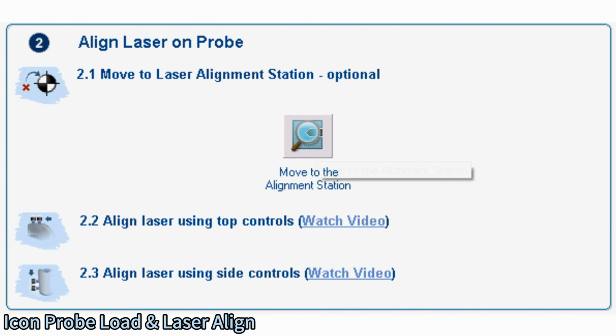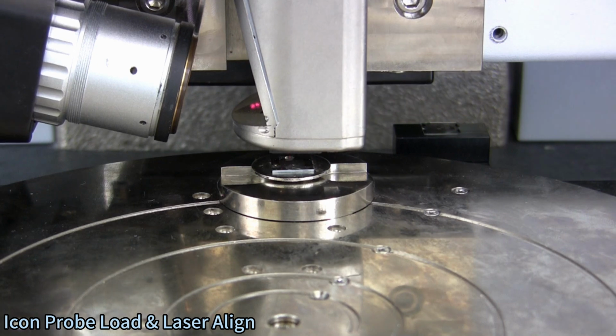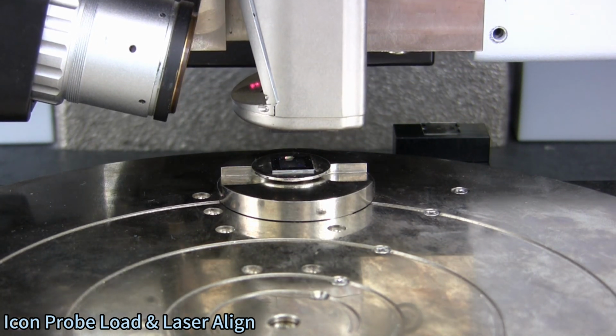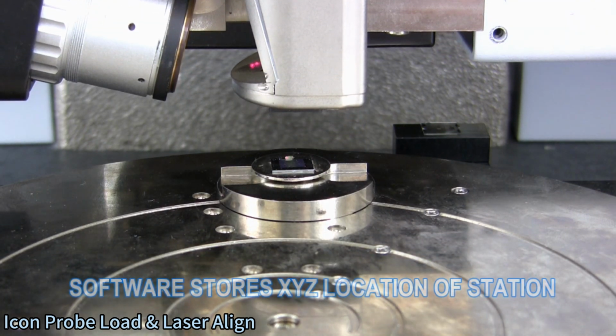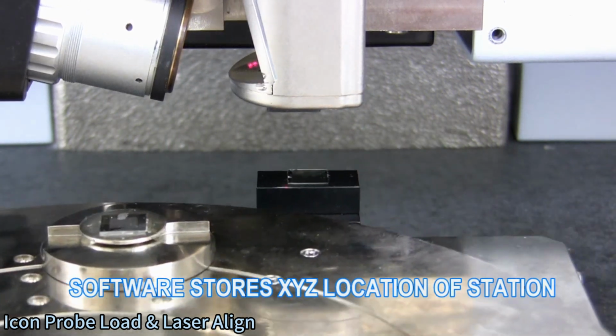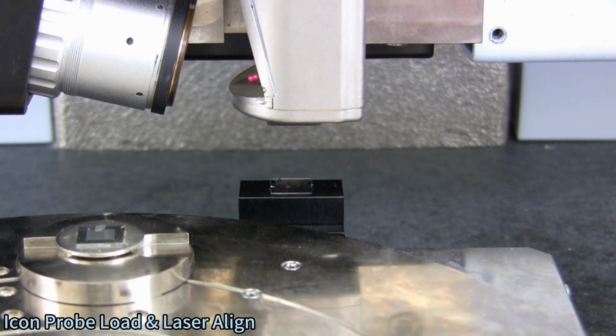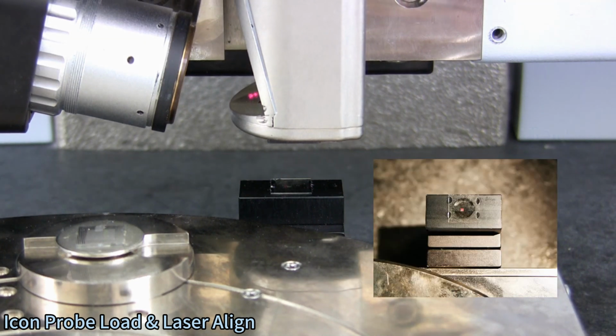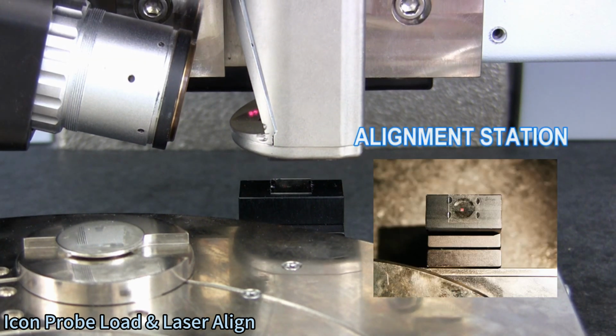Use the software command Move to Alignment Station in the Setup screen menu to translate the stage forward. The station is located near the back of the sample chuck. This allows the probe to be placed above a reflective surface so that the image of the laser spot and the mirror image of the cantilever can be viewed at the same time.